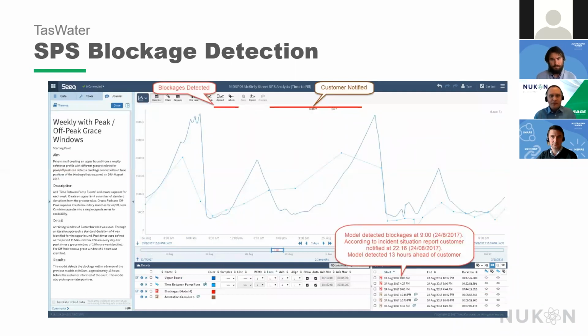The key thing to really look at here is the reference incident, which occurred on the 24th of August 2017. We retrospectively applied our model to that incident, because that was really the driver for the project. We needed to be able to detect not only that incident, but also new incidents of a similar type, which is a partial blockage, meaning the automation system won't necessarily tell you there's a problem. It won't alarm — everything looks normal, but meanwhile you're actually spilling upstream from the pump station because maybe a blockage has started to form upstream.